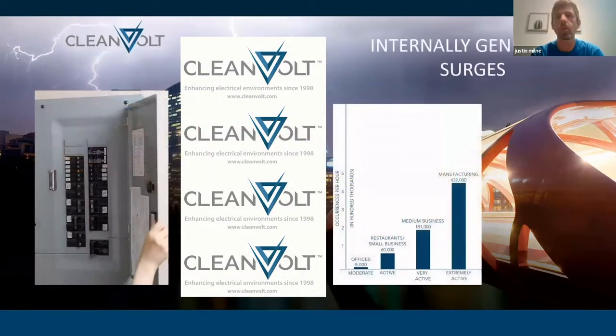The third set that we'll go over is internally generated surges. On your left-hand side, you'll see that there's a power panel. And of course, this load center, all the connected devices on it are sharing the same common power source. And as devices turn on and turn off, or your electronics are on, creating harmonics, the energy surges caused by these actions are being felt by every device shared on this load center.